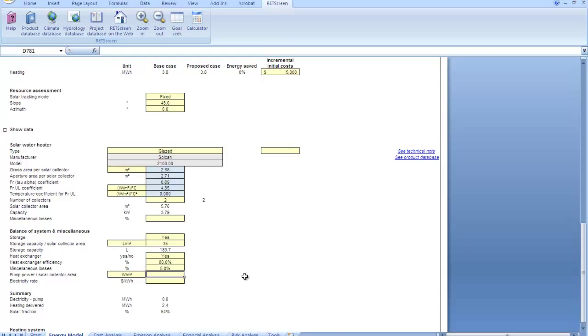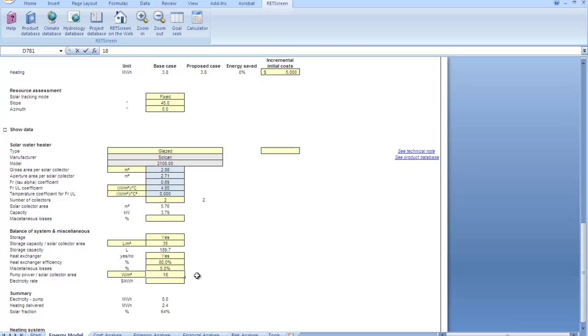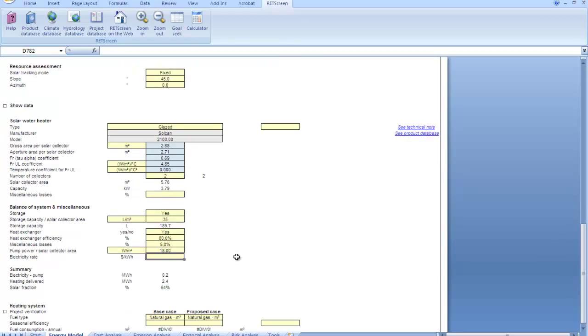We are going to have a heat exchanger in this system in my example, so I'll choose yes for the heat exchanger. And I will put 80% efficiency for the heat exchanger. The heat exchanger efficiency has to do with how well the heat transfers from one fluid to the next. It doesn't mean that it's 80% efficient and 20% goes to waste. Our storage capacity is expressed as liters per square meter of collector. A little bit awkward for small systems. Usually we know how many liters our storage tank is going to be. For instance, a 200 liter tank is pretty typical. So if I choose 35 liters per meter squared with a two collector system based on these areas, then it turns out to be 200. Again, we have, rather than entering the watts of the pump directly, we have watts per square meter of collector. I know my pump is going to be something like 40 watts on a system like this. I'll enter 18 watts per meter squared as my pump power.